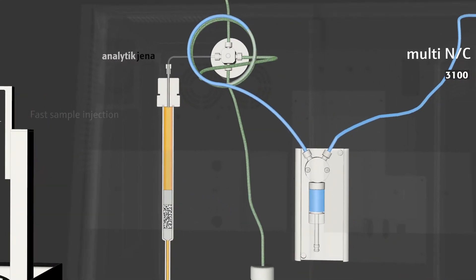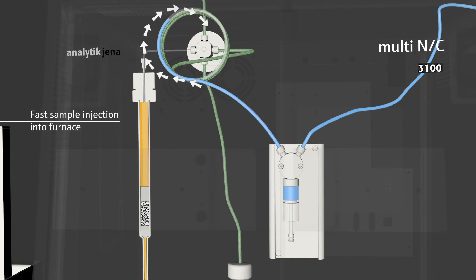A robust ceramic valve guarantees optimum particle handling. The sample is injected quickly and all particles are completely transferred from the injection loop to the furnace.